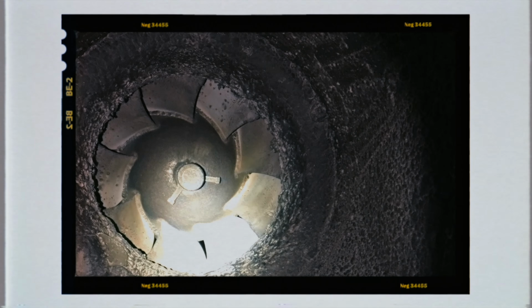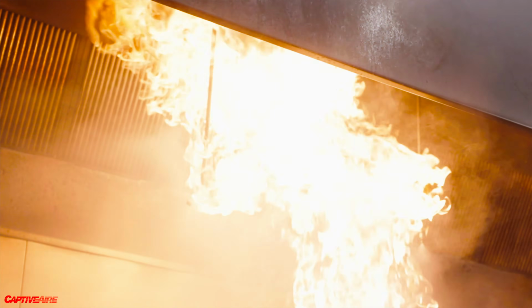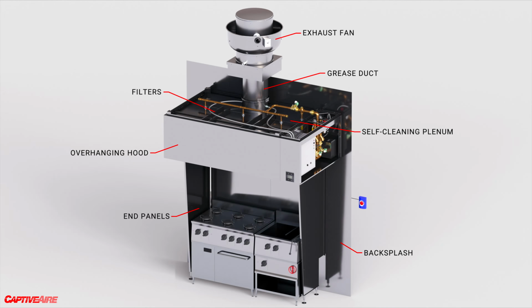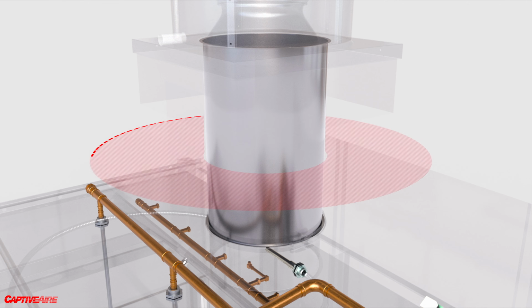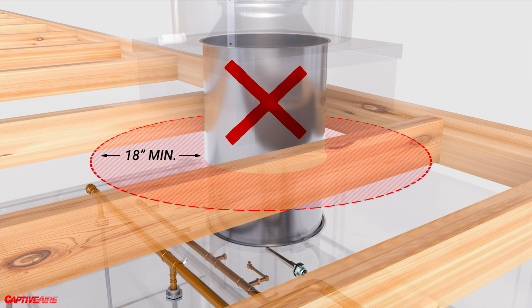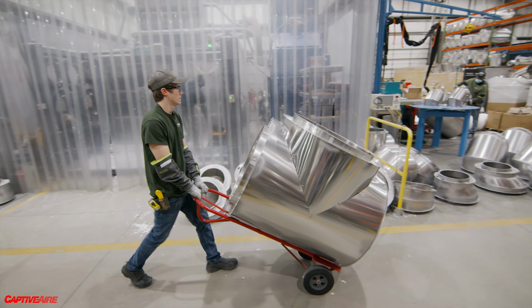When hood plenums and ducts are neglected over a period of time, I've actually seen duct diameters be cut in half due to grease load. You can have inches of grease build up inside of a hood and duct system. That's all fuel for a fire. There are different grades of grease duct. There's non-insulated. That's suitable for areas where you have at least 18 inches of clearance all around the duct. But if you have combustibles near the duct within 18 inches, you need insulated grease duct. And that insulated grease duct is a very good passive fire suppression system. It will contain fires and prevent those combustible surfaces from igniting.